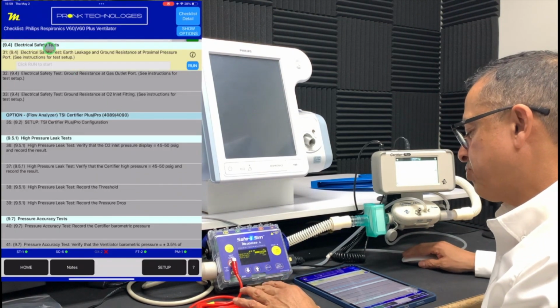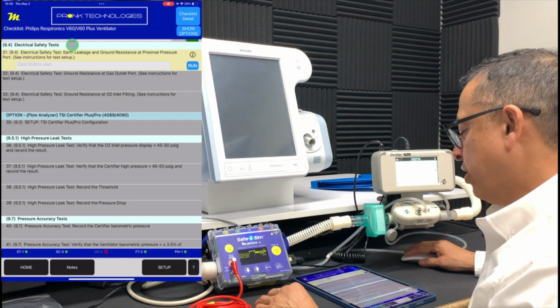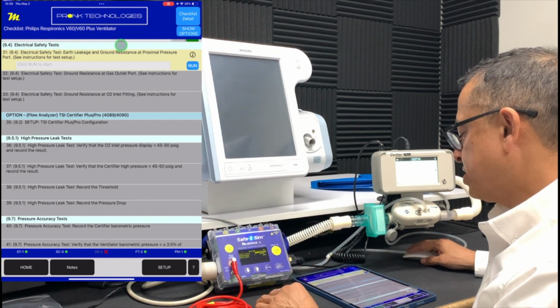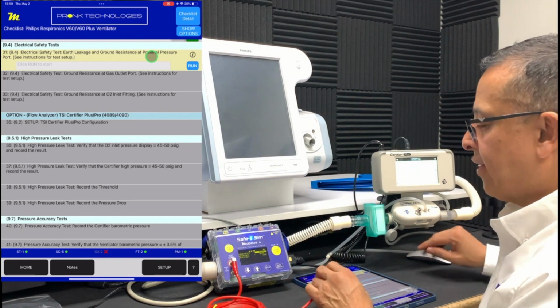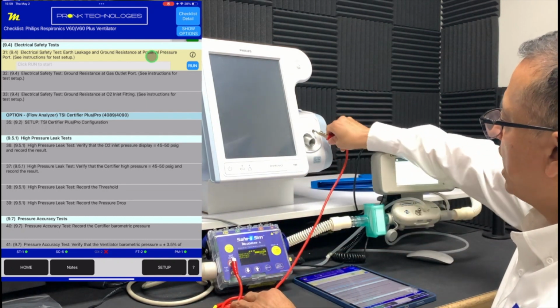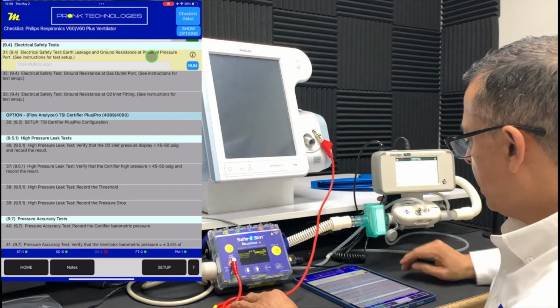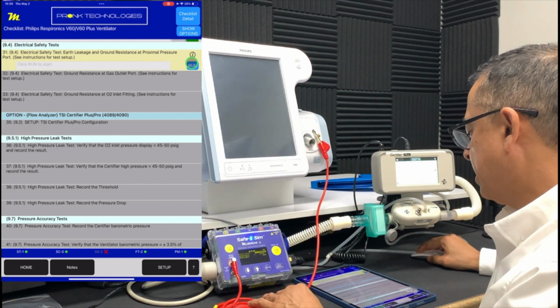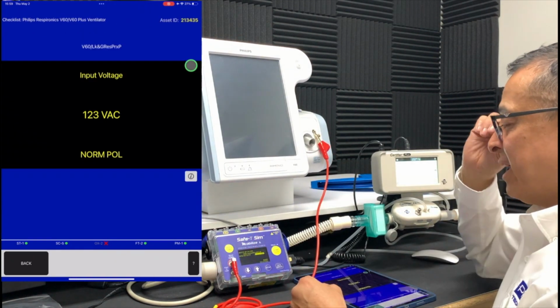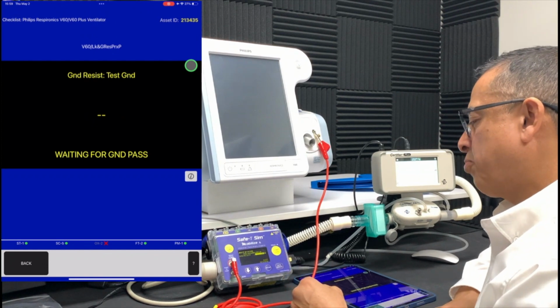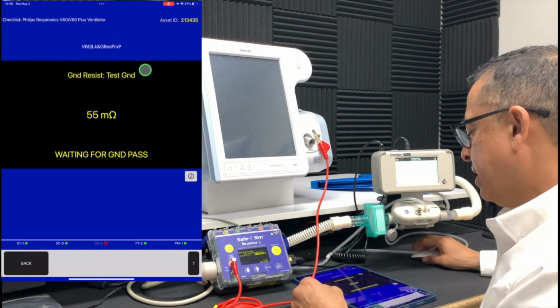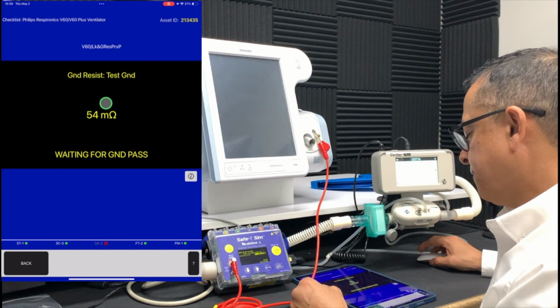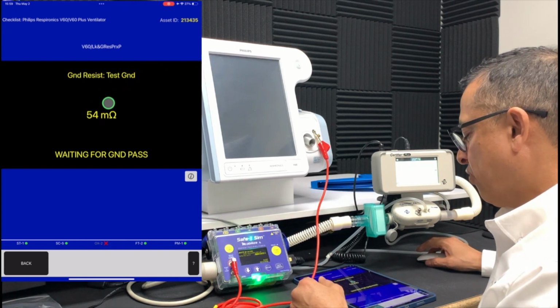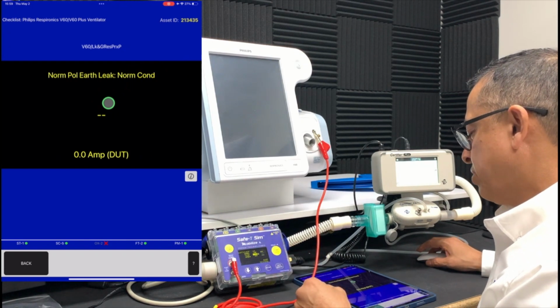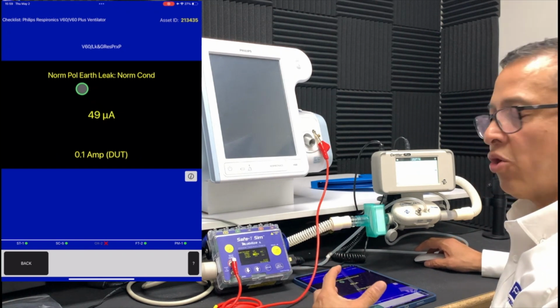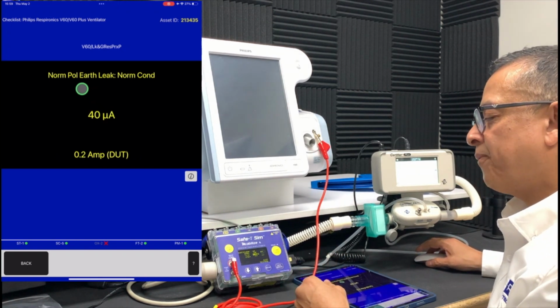So the next step in this procedure wants us to do the earth leakage test and ground resistance test to the proximal pressure port on the front of the unit. So I'm going to take my test lead cable, connect it to here, and hit run to execute those tests to the safety analyzer. When I do that, it's going to start the safety analyzer and perform the test. You can see here on the app, you're going to get a ground resistance measurement. It's going to accept that result after it realizes it's stable, and then it's going to do the earth leakage test under normal conditions.